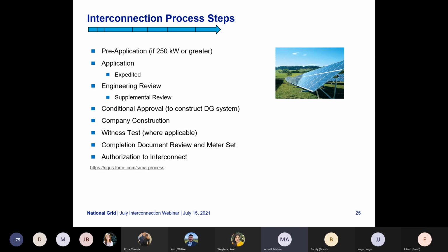In the screening process with engineering review, if it's determined that a supplemental review is required, we would go through the process of doing a supplemental draft and an agreement, and then using our engineers to get a little bit further detail to come up with cost. At that time, we would give an ISA and give conditional approval to construct the system. If it did not follow the supplemental review and it was straightforward and no system improvements were needed, or it was just a standard upgrade, again, we would establish an ISA, whether there was cost or no cost, and we would deliver that to you.